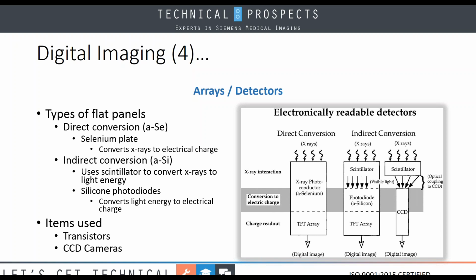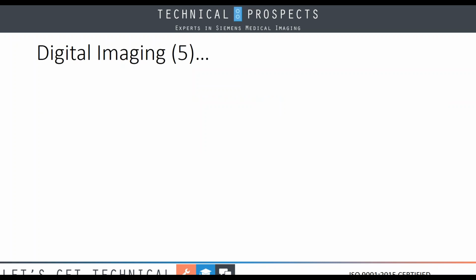All right. As you can see, we have two different types. We can have transistor type detectors or CCD camera detectors. And again, this is strictly dependent on the design of the system that you're servicing. From here, when we look at the construction of flat panels, we notice we have two different types: direct and indirect. If you liken this to the world of film, we talked about direct exposure film and light exposed film. This is basically the same thing that we're looking at here in flat panels. So the panels are just an outgrowth of our film industry.